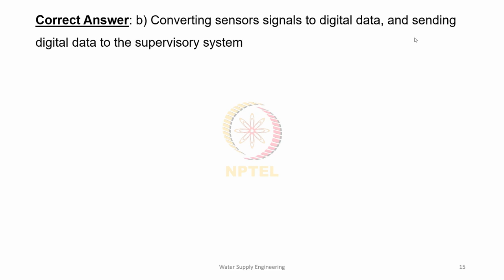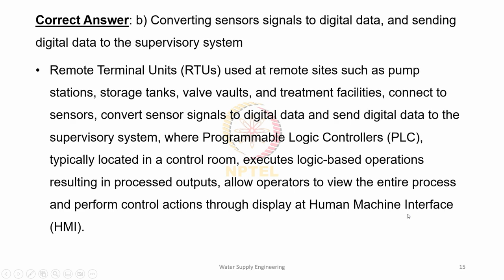So the remote terminal units used at remote sites, for example pump station, storage tank, valve vault, and treatment facilities, are connected to the sensors. They receive the data from the sensor and convert that to digital data, which is later sent to programmable logic controllers in a control room, where an executive professional or personnel will be available to execute logic based operations and give out processed output. So at the end, the operating personnel will be able to view the entire process and perform the control action through a human machine interface.